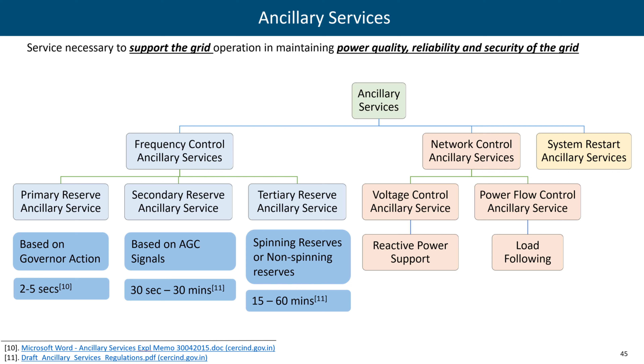Why do we need system restart services? Can anyone tell? For a grid failure or blackout, we have to restart the system. Yes. These generators—huge thermal or nuclear generators—have auxiliaries required to start the plant. So if the plant is shut down, where will they get the power from? That is provided by generators which can act fast on their own, without any external requirement—these can be big diesel generators. Storage can also provide this service.